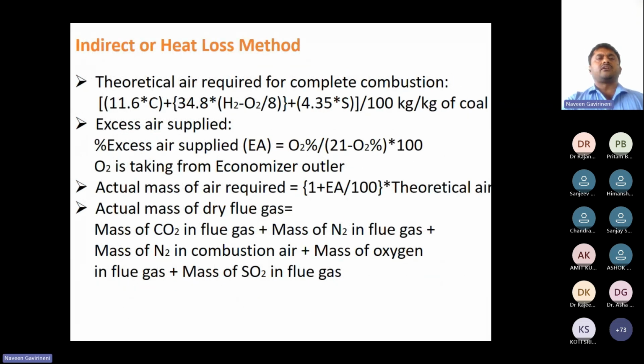So this is the theory. This is the calculation part. From the theoretical air requirement formula we get how much theoretical air is required. I have already explained two types of air: one is theoretical air and the other is excess air. So this is the excess air formula. This O2 we take from the economizer outlet. So O2 by 21 minus O2 gives the excess air.